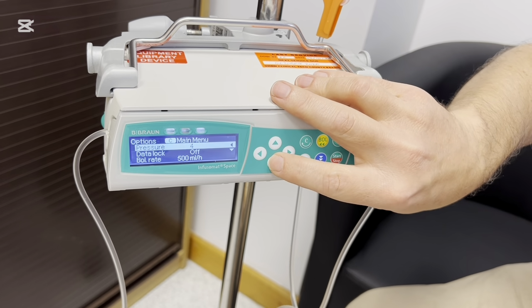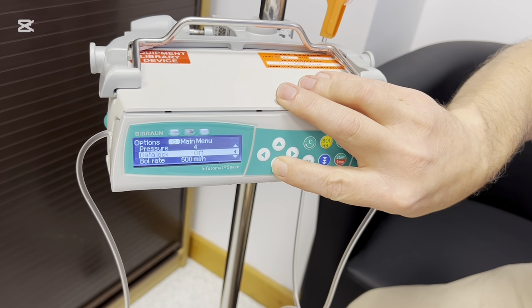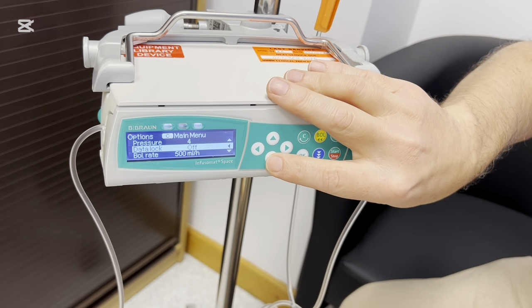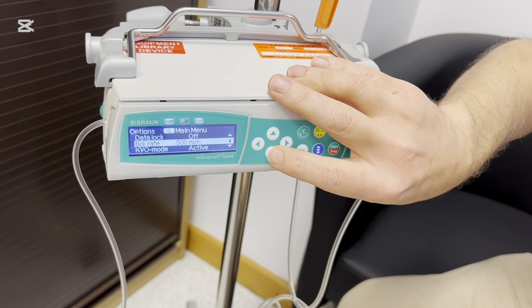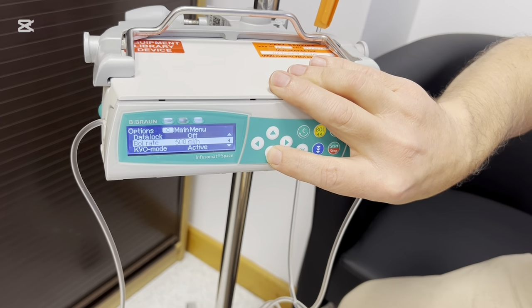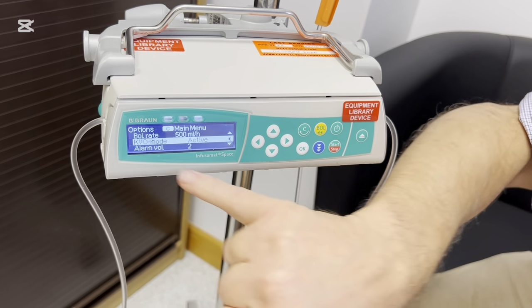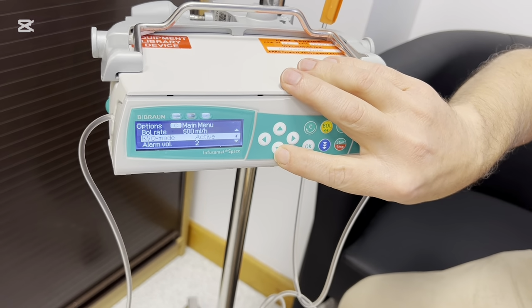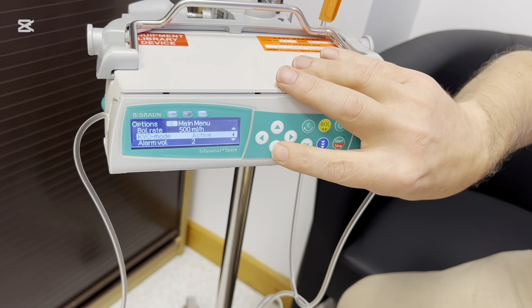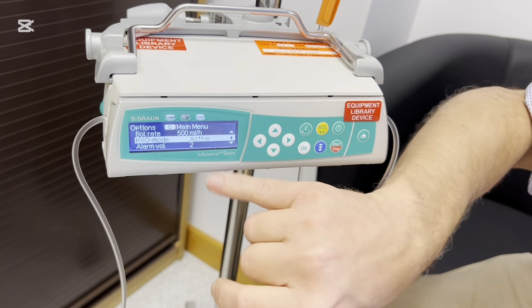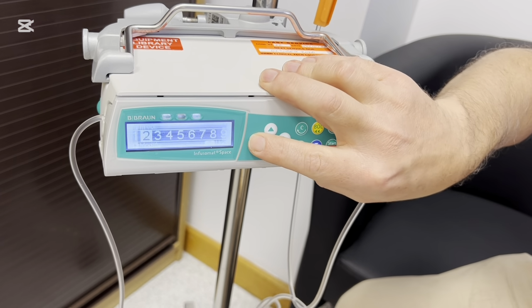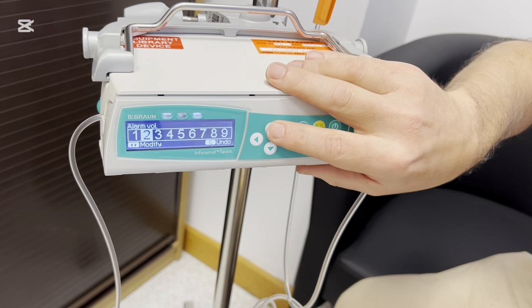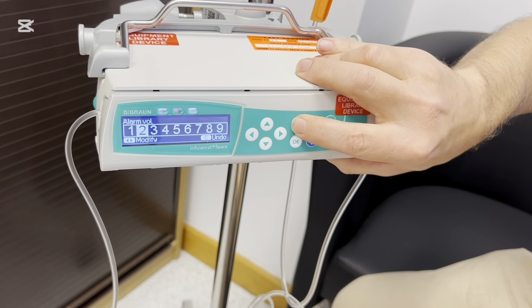Whilst we're on the options menu, there's other selections. The data lock is not relevant. The bolus rate, again, not particularly relevant, but can set it if we want to. Keep vein open mode is active, so when it gets to a few mils left, it will switch into a much lower rate mode just to keep the vein open. And then you can select the alarm volume, 1 to 9. I won't go through it. If we press the C, that'll take us back to the previous menu.